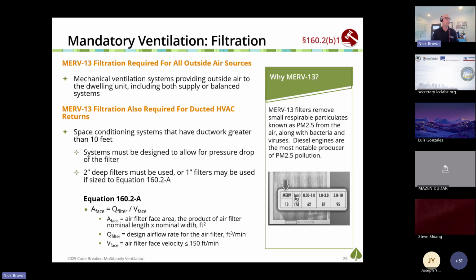Also in the category of mandatory requirements for ventilation is filtration. You all know we went to a MERV 13 requirement on ducted returns for HVAC systems. Well, we also have a MERV 13 filtration requirement for all supply fans bringing in outdoor air. Whether they're part of a balanced system or just a supply system, you've got to have a MERV 13 filter on that. This ensures that, let's say we've got a forest fire going on affecting air quality in your area. Well, that MERV 13 filter is going to really benefit those occupants to filter out much of those particulate matters. They also, by the way, catch things like PM 2.5 from diesel particulates and even bacteria and viruses. So a real nice selling point on health and safety of buildings.